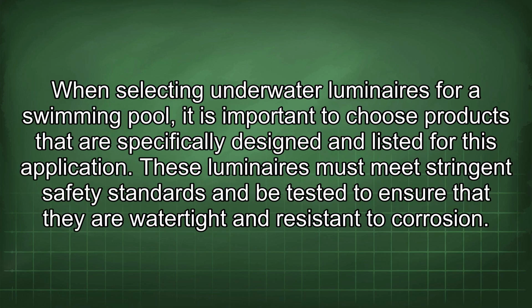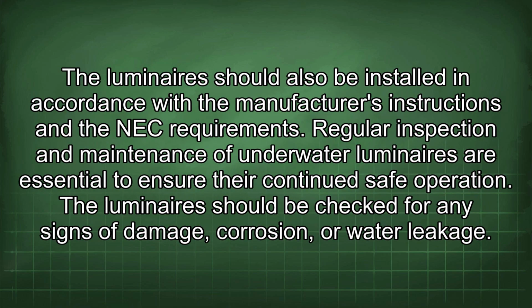When selecting underwater luminaires for a swimming pool, it is important to choose products that are specifically designed and listed for this application. These luminaires must meet stringent safety standards and be tested to ensure that they are watertight and resistant to corrosion. The luminaires should also be installed in accordance with the manufacturer's instructions and the NEC requirements. Regular inspection and maintenance of underwater luminaires are essential to ensure their continued safe operation.